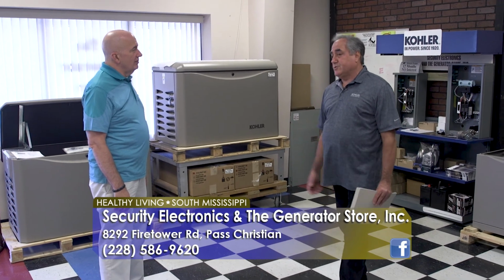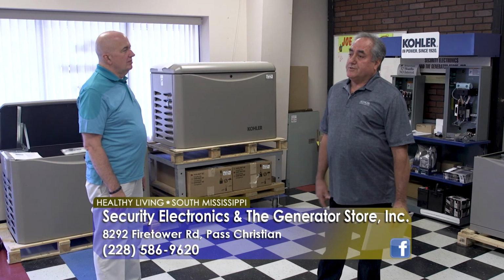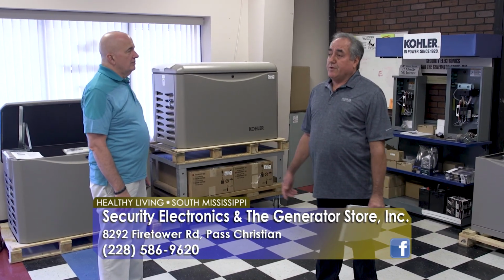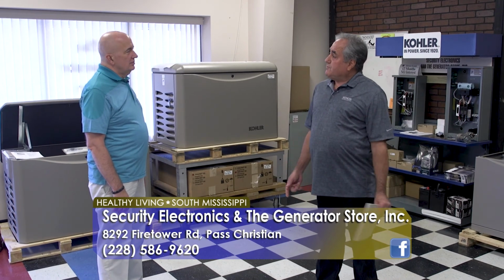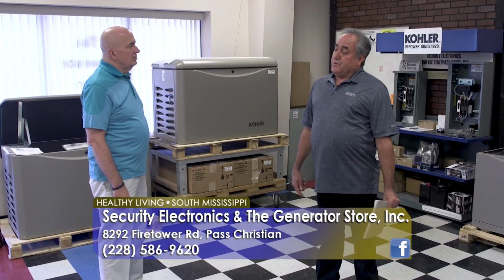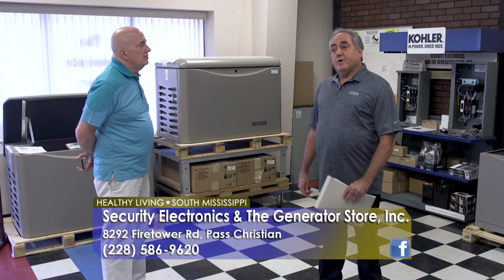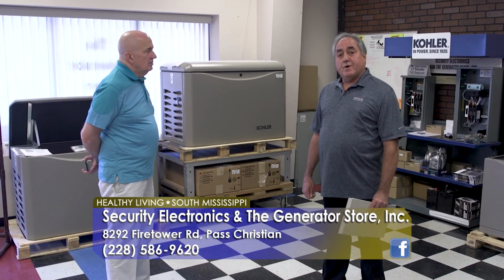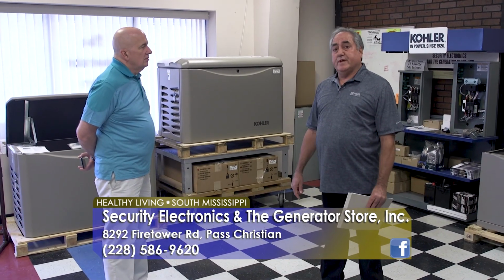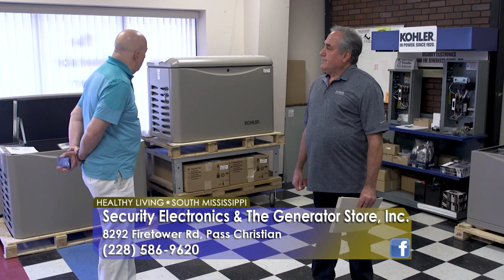Absolutely. The whole house generator is really the way to go. So the utility power goes out, the generator starts up, and transfers over to generator power. Within about 10 seconds, you're on generator power. The only thing you have to do is wait about 10 seconds for everything to transfer over. Then the generator will run continuously until the utility power returns. The generator system will sense that, and it will know that it needs to transfer back to utility power. It'll do that, and then the generator will go into a cool down process and shut off and wait till the next time.